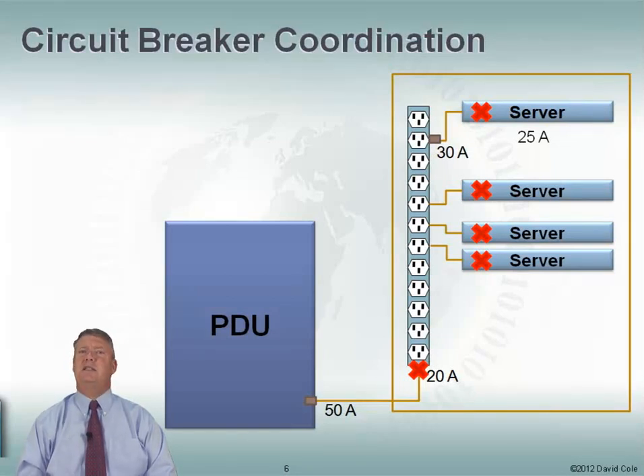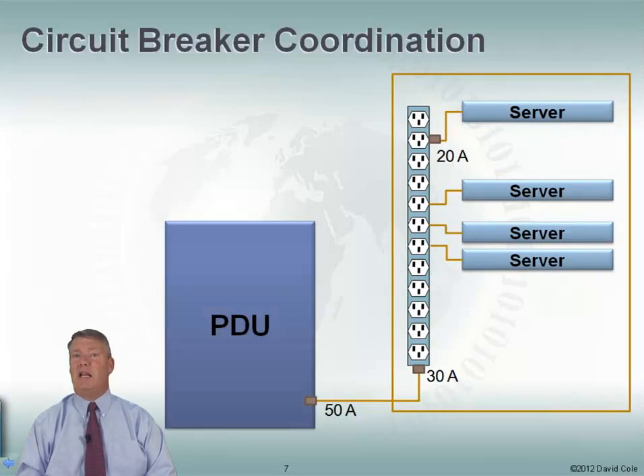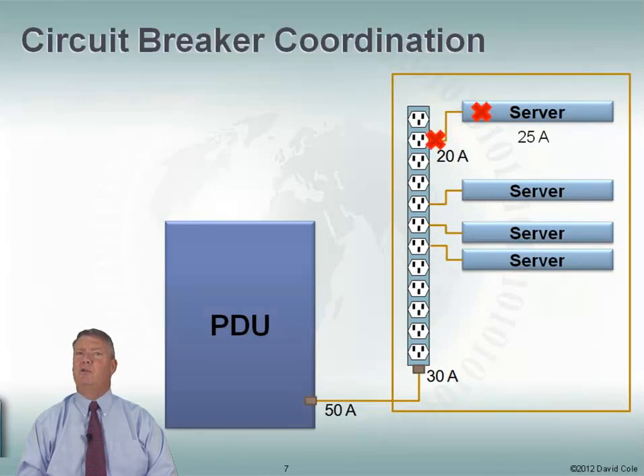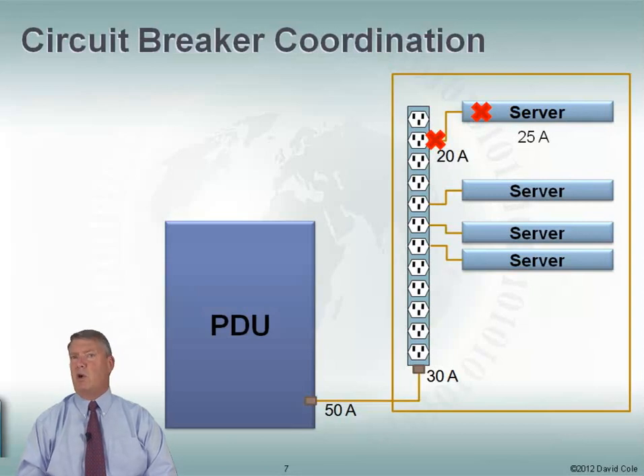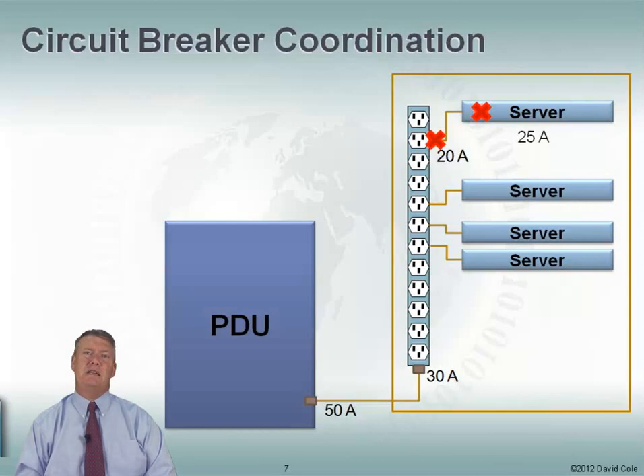This is bad circuit breaker coordination — this is not what we want. Instead, what if we switch these breakers around? If I had a 20-amp breaker at the outlet level and a 30-amp breaker at the rack power strip level, then when a server draws 25 amps, that's the breaker that pops. I lose that one server, but my other servers are blissfully unaware that anything happened. This is much better circuit breaker coordination — if I'm going to blow a circuit, I want it to blow as close to the equipment as possible and take down the least amount of equipment.